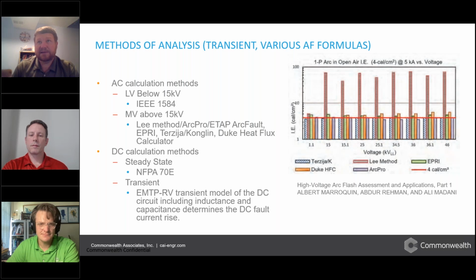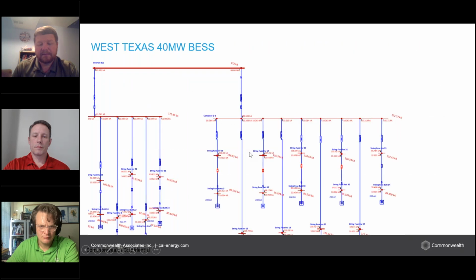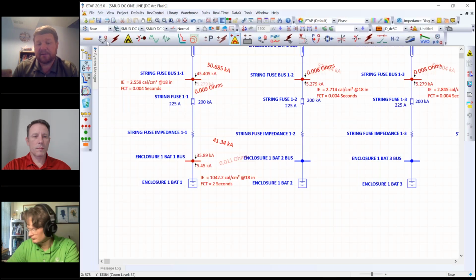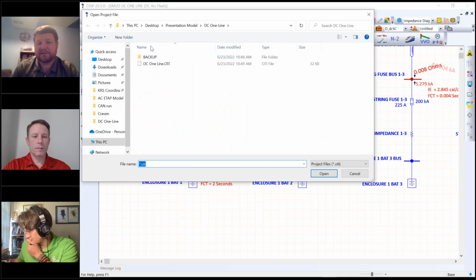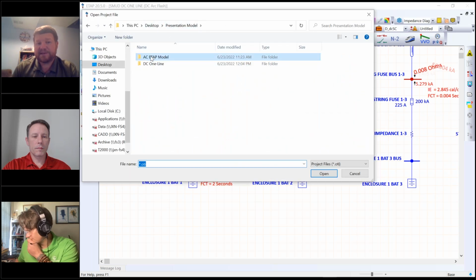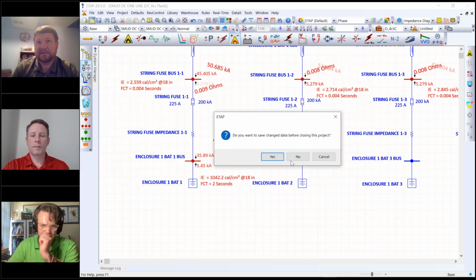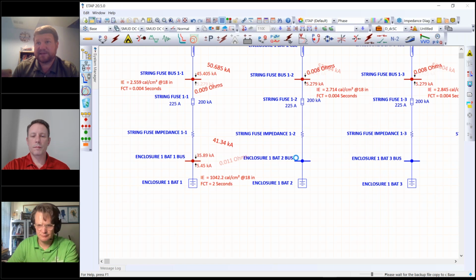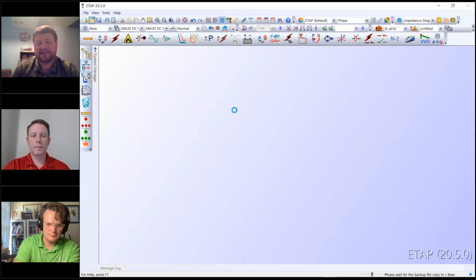So yes, on the AC side. On the DC side, that's where we do the transient analysis and we look at the effects of those CLF fuses. So Chris, if you go to your example, even where we weren't seeing any pickup on the AC for the transformer secondary fault locations that were showing up around 100 cals, that's accounting for the action of those CLF fuses. The CLF fuses, even though they're supposed to be a current limiting fuse, they still weren't fast enough to clear that low side fault. That seems a little counterintuitive, but that's what the analysis shows on this particular example.